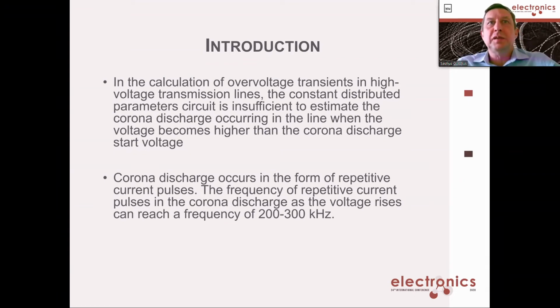In calculations of overvoltage transients in high voltage transmission lines, we usually use distributed parameters of the power line. In electronic devices you use capacitances, inductances, and so on, but in calculations of electric power lines you use distributed parameters, meaning it's not just capacity, but capacity distributed through all the line. It's a little different understanding, but it comes from Maxwell's equations, from the modeling of wave equations. If you would like to model a power line precisely, you should use distributed parameters.